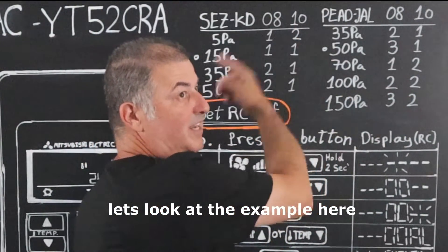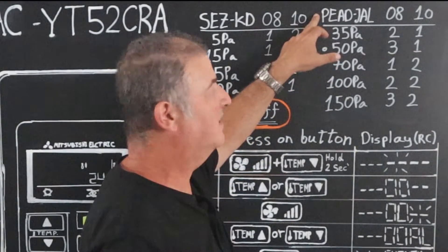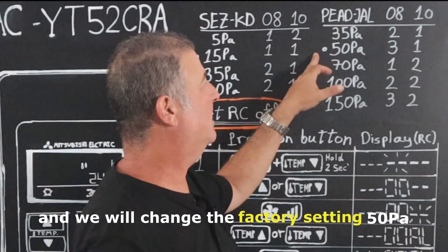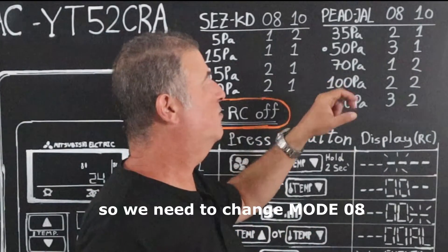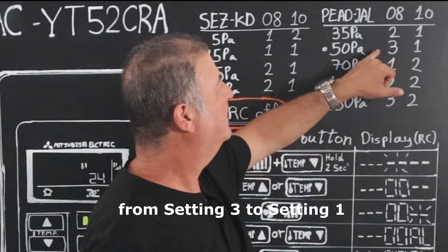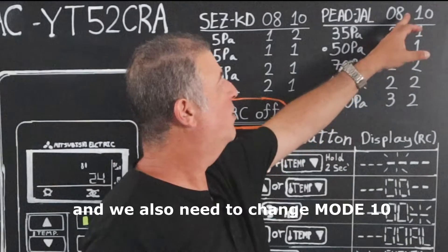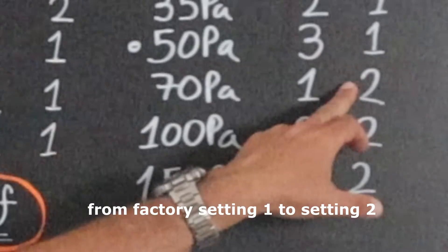Let's look at the example here. We will take the PEAD-JAL indoor unit and we will change the factory setting of 50 Pascal, increasing it to 70 Pascal. To do this, we need to change mode 08 from setting 3 to setting 1, and we also need to change mode 10 from factory setting 1 to setting 2.